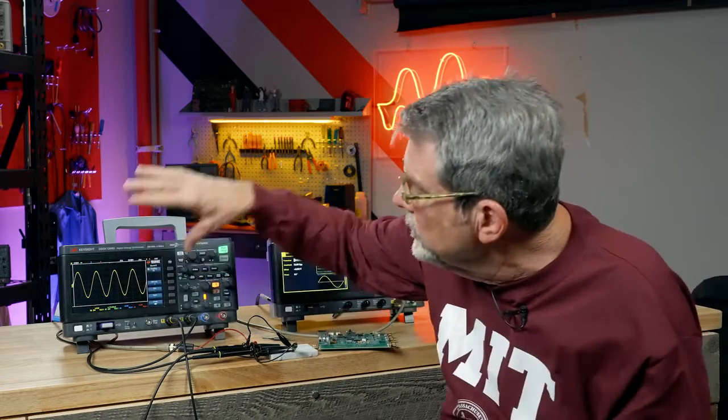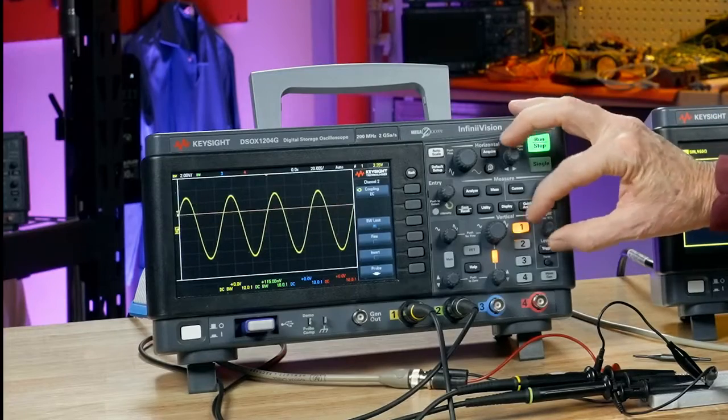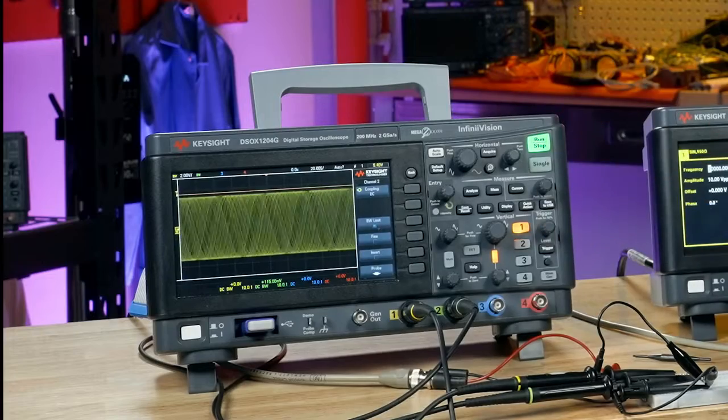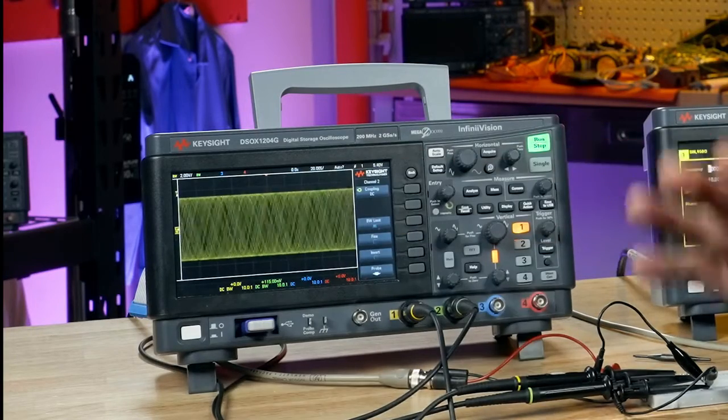Now, it may look to you like that's just a single stored waveform, but it's updating very quickly. If I move the trigger level up, as you saw in the earlier lesson, we lost trigger and all we see is a blur of waveforms. What's happening now is the scope is throwing up those 200,000 points in a random location. This is supposed to be synchronized picture taking. Now it's unsynchronized display of pictures.